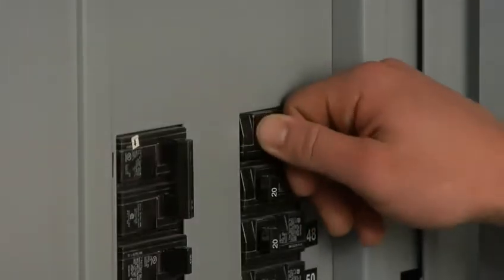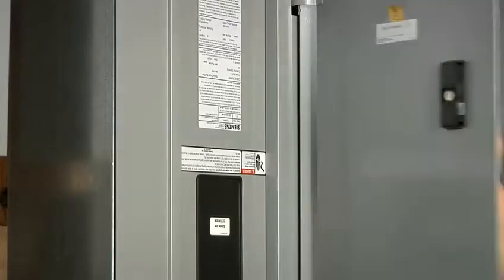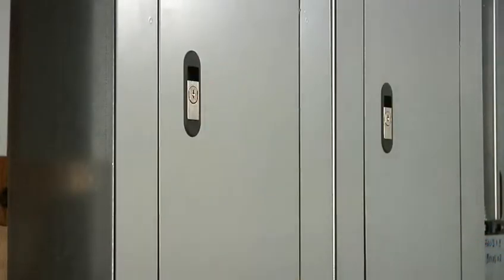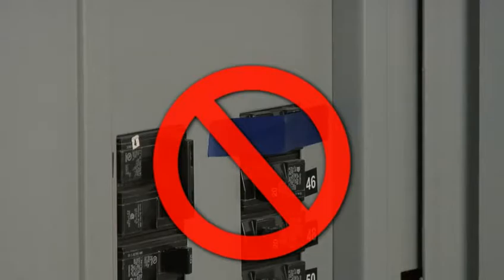Circuit breakers are also something to be aware of. You want to maintain circuit breakers safely by following these simple guidelines. Keep a 3-foot clear area directly in front of all electrical panels. Make sure panel box covers are closed at all times. Never tape circuit breakers to prevent them from tripping. And of course, be sure you report any problems such as breakers that keep tripping or breakers that aren't clearly labeled to restaurant leadership.